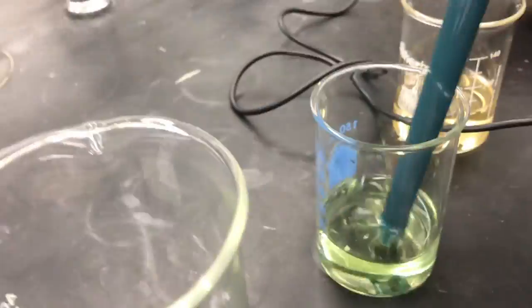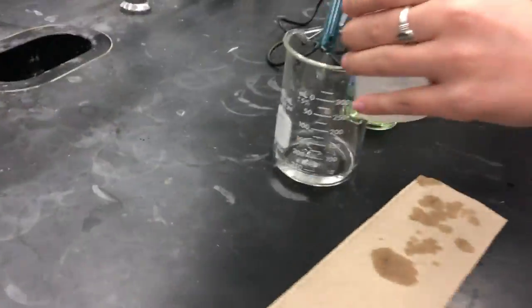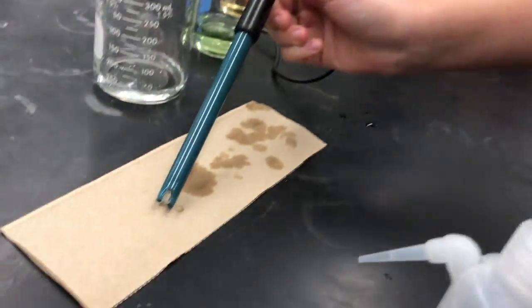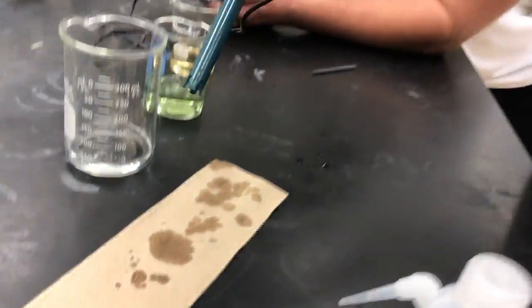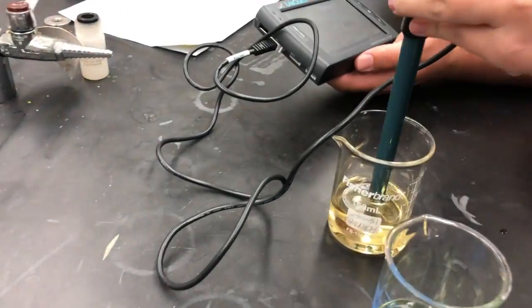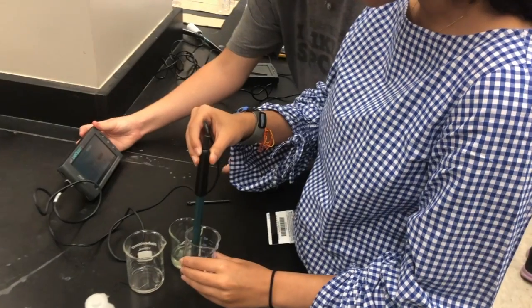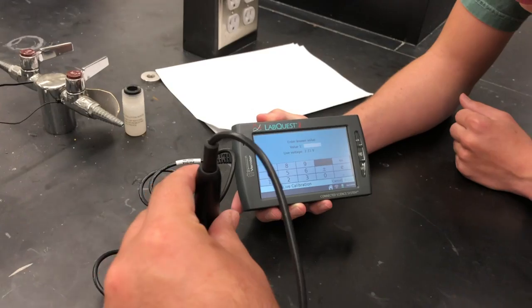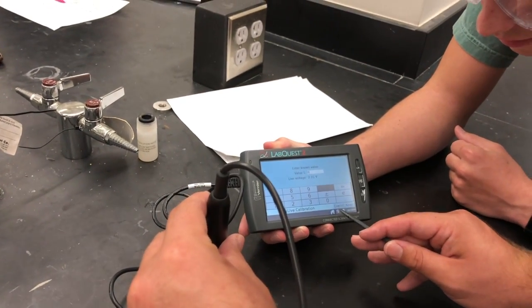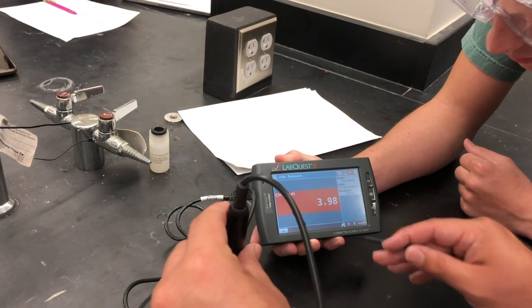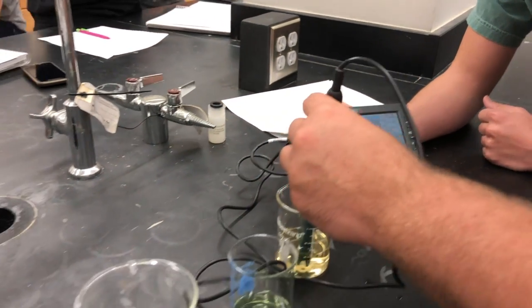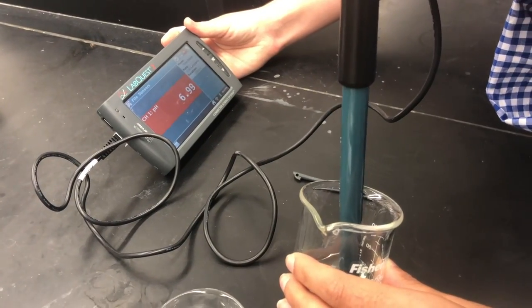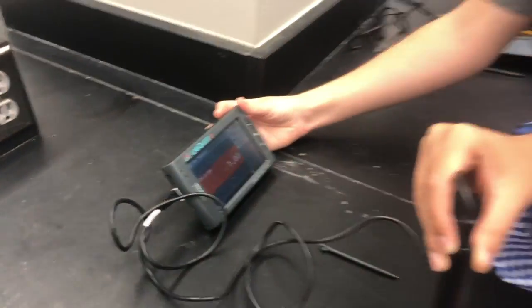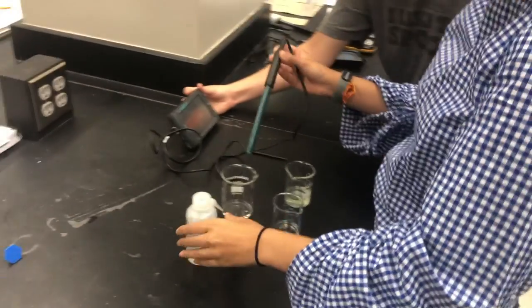Then, after washing the probe again in distilled water, you can then place it in your second value buffer solution with a pH of 4. Then, once the meter has stabilized, you can record the pH value of 4.0 into the LabQuest. Once you have completed that process, you are done calibrating your probe. To be sure, if you would like, you can replace your probe back in the 7 buffer solution and see if the value of the pH meter reads as 7.